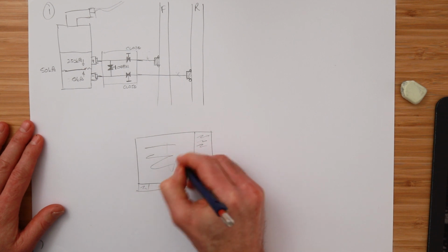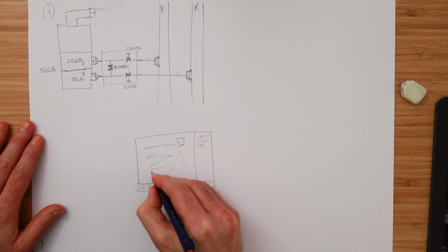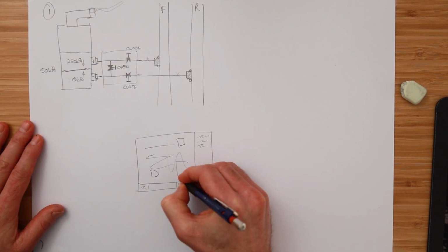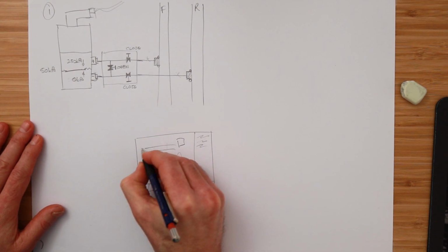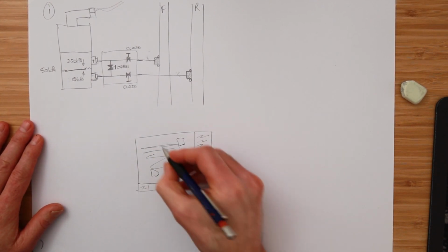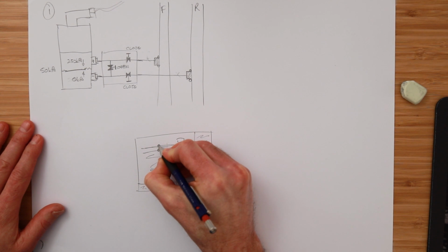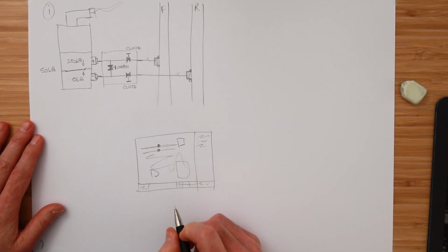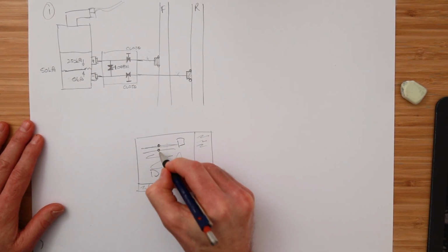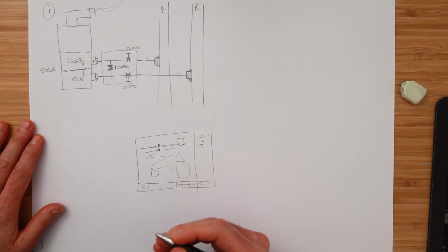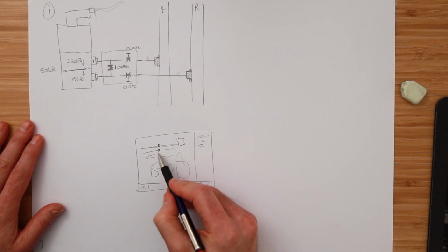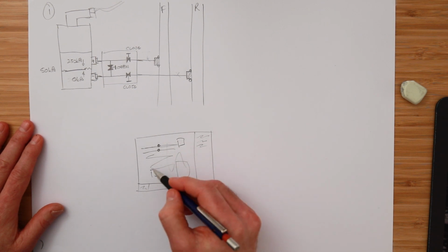Here's our chilled water schematic, and there's pipes everywhere. There's something over here, and there's a thing over here, and there's a plant room here. And you determine that on the chilled water schematic, this is the best location for the mechanical fitter to weld in these sockets. That's where you want it. That's a good representation of the load. You need to get the layout drawings that show the pipework runs, or go to site and have a look at this.